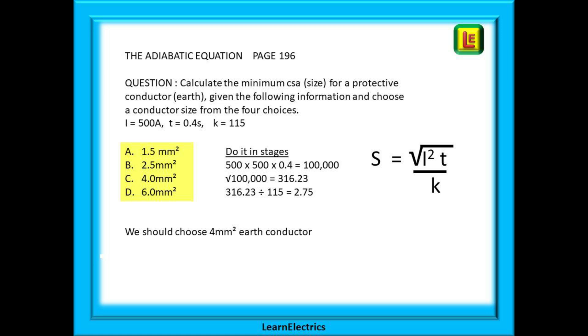Do the calculation in stages. Follow it through as shown here and you should get an answer of 2.75 millimeters. Now make your choice from those offered and we should choose 4 millimeter conductor. We have a full video on the adiabatic equations and we will leave a link in the description to this video.